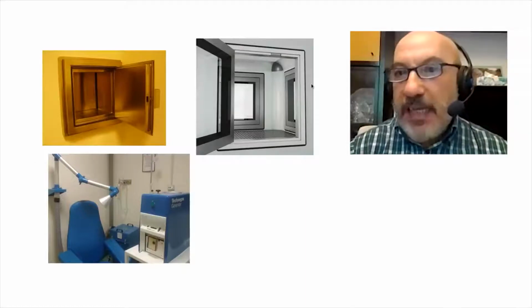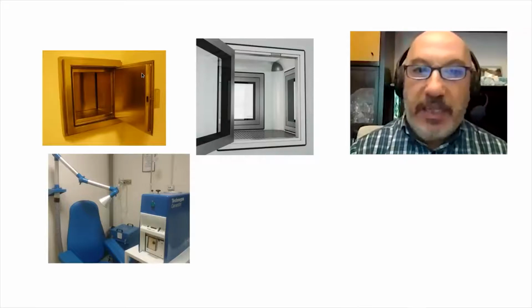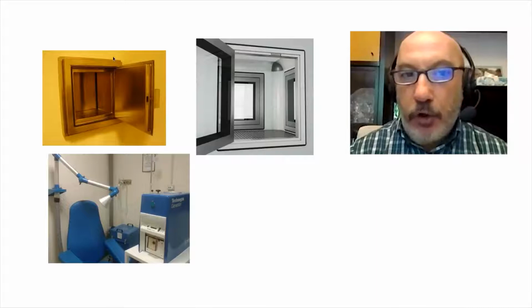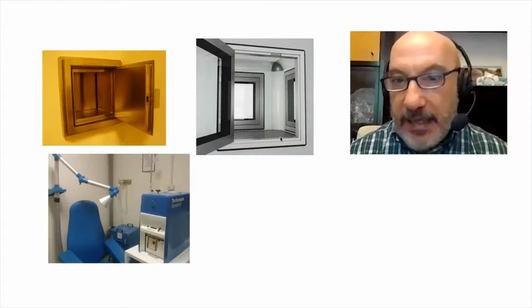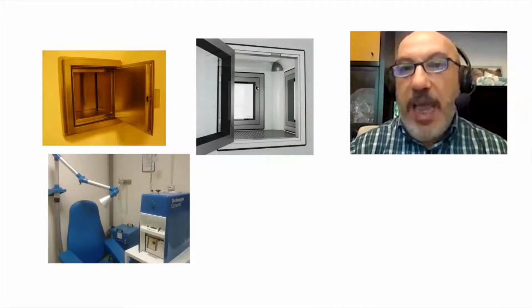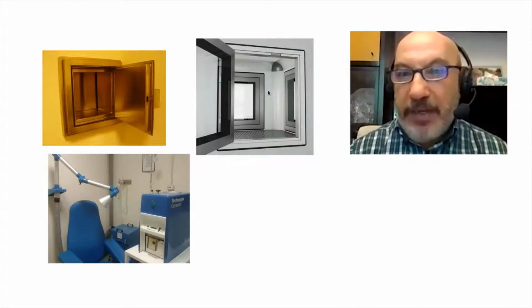In order to realize the proper communication between the laboratory area and the administration room, so-called pass-through boxes are a very good solution. You can see here that this one is not vented, while this grid tells you that this is a vented pass-through box, and they may be necessary, depending on the type of pharmaceutical classification of the laboratory.